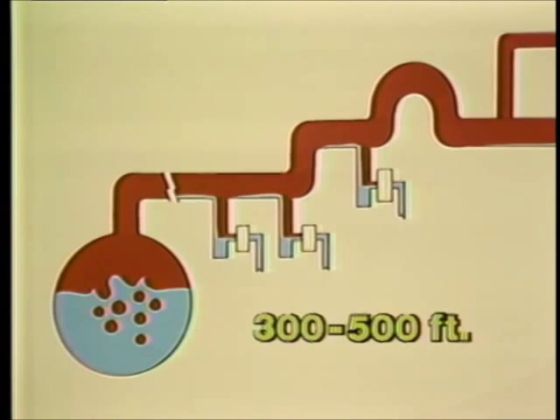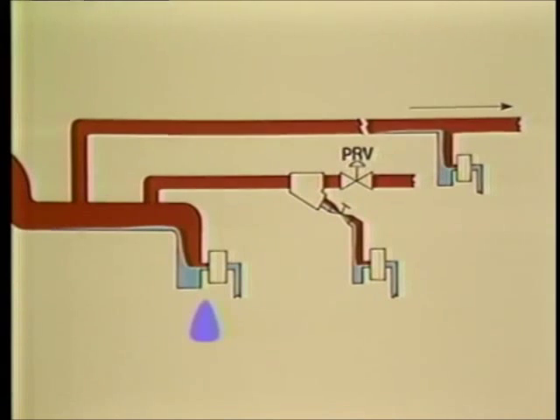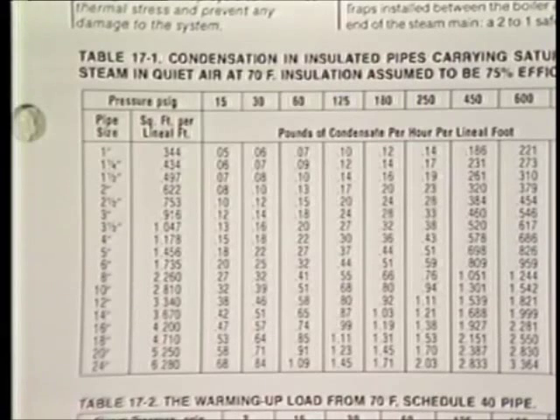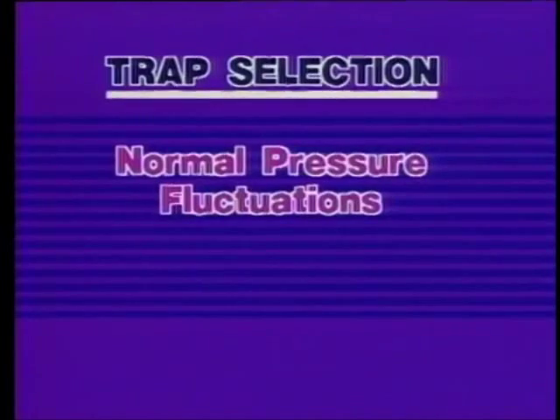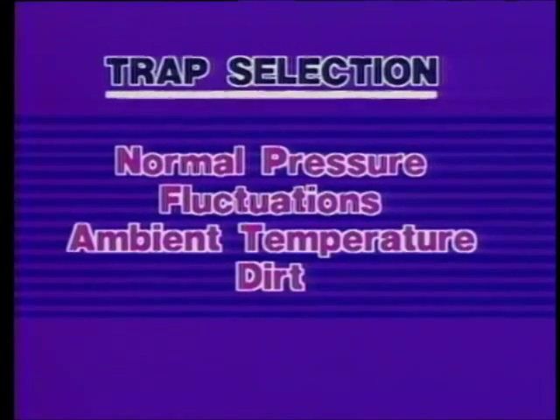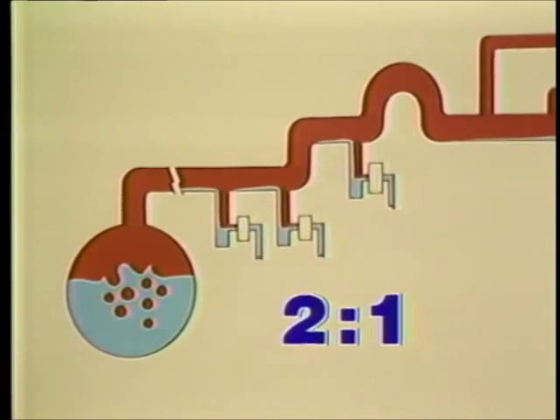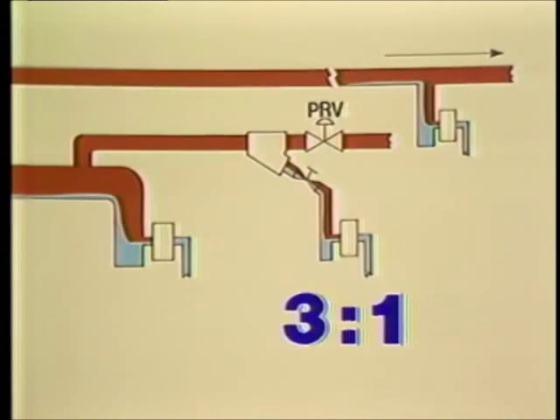Steam mains should be dripped every 300 to 500 feet. Also, install drip traps immediately ahead of risers, expansion loops, pressure-reducing valves and temperature regulators, at the end of steam mains, and on long runs of branch lines. Select a trap based on the calculated condensate load, not on the pipe connection size. Other considerations in trap selection are normal steam pressure, fluctuations in pressure, ambient temperatures, and the likelihood of dirt in the system. Use a 2-to-1 safety factor for drip traps between the boiler and the end of the main. Use a 3-to-1 safety factor for the trap at the end of the main and for traps ahead of shut-off valves, pressure-reducing valves, and temperature control valves.